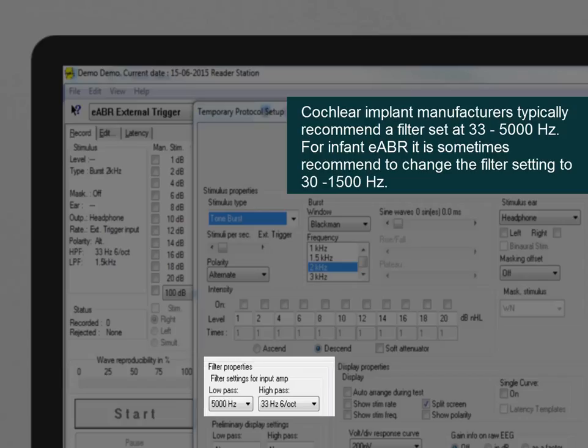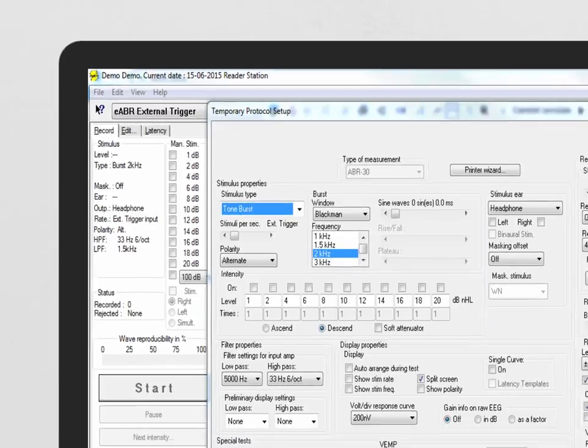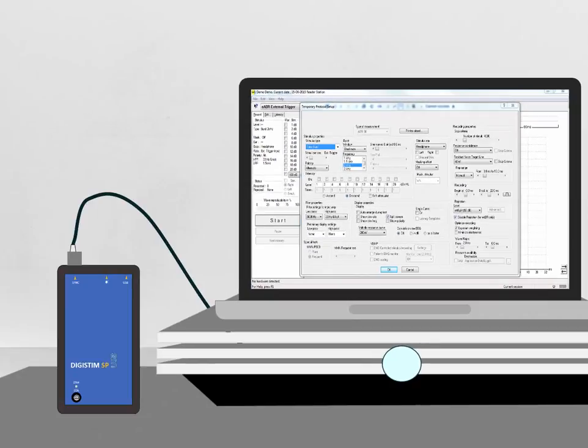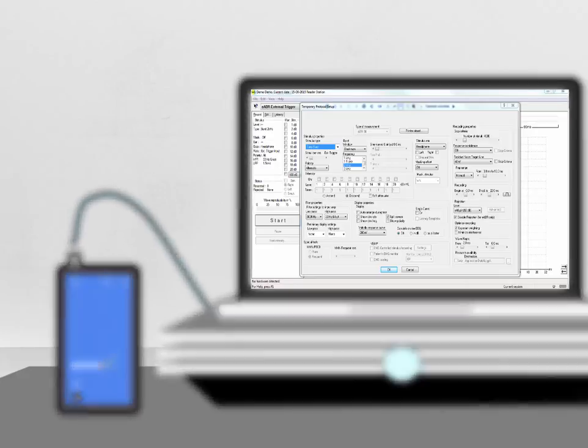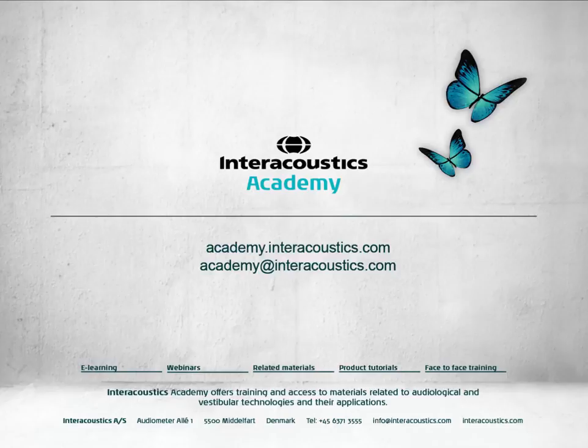The final setting that needs to be adjusted is the filter setting for the input amplifier. Cochlear implant manufacturers typically recommend a filter set at 33 to 5000 Hz. For infant eABR, it is sometimes recommended to change the filter setting to 30 to 1500 Hz. Each implant works differently, therefore it is important to consult the manufacturer's test parameters and preferences before testing. This concludes this quick guide video on setting up the system for eABR testing.